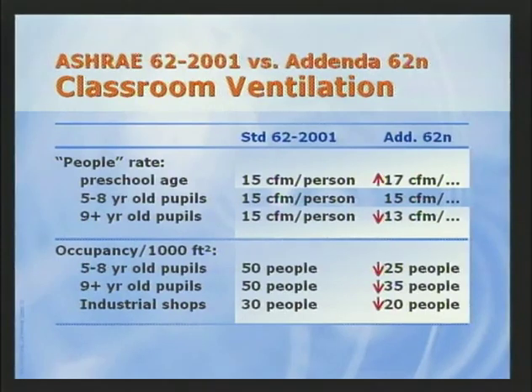Metal and woodworking shops, referred to as industrial shops in previous standards, now have the default occupancy value of 20 people compared to the 30 people per 1,000 square feet in the earlier standard. This reduction in occupancy reflects the movement throughout the education industry towards smaller class sizes. Although the resulting amount of ventilation required for classrooms doesn't change much, there are significant changes in the way the designer arrives at the zone ventilation rates.